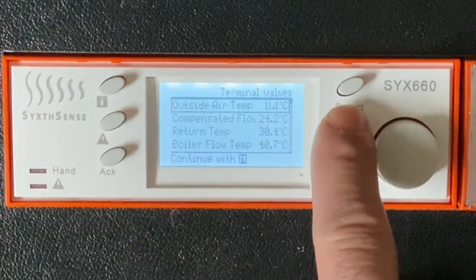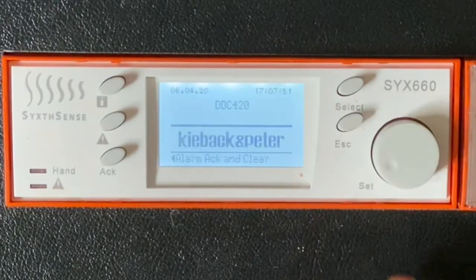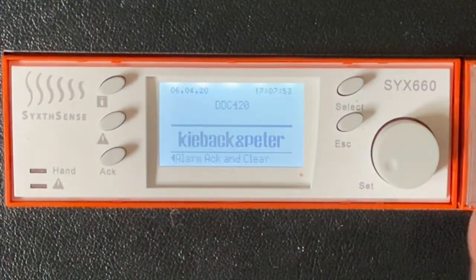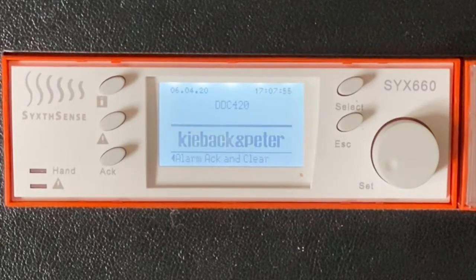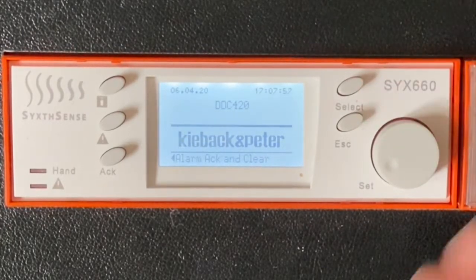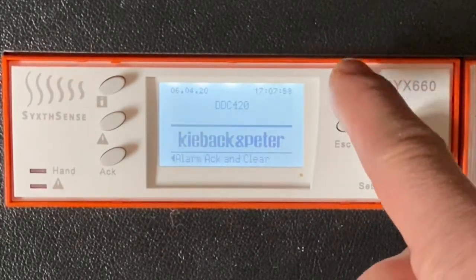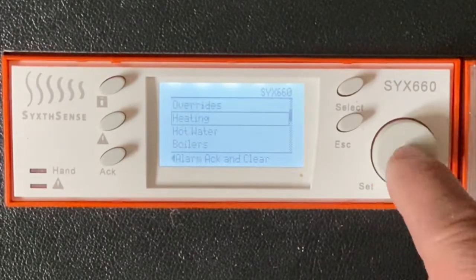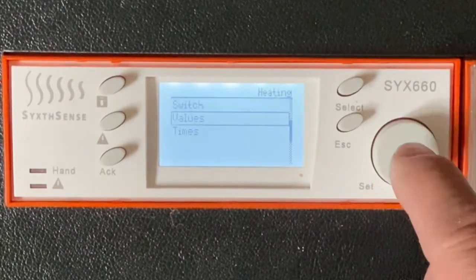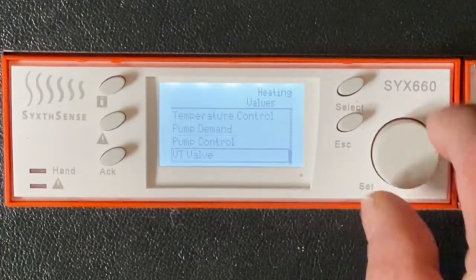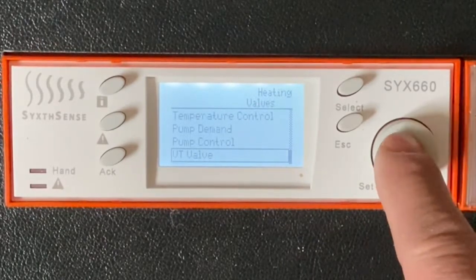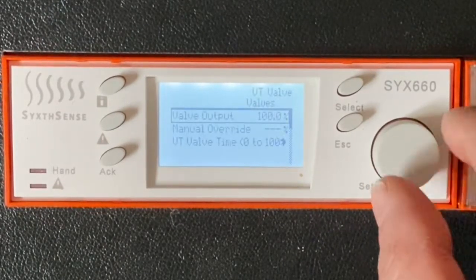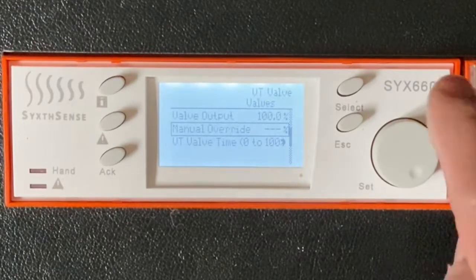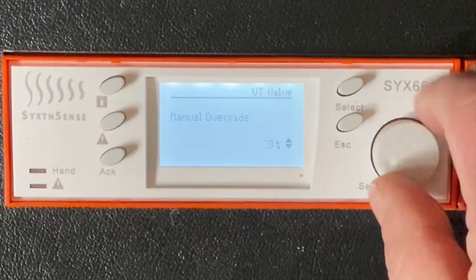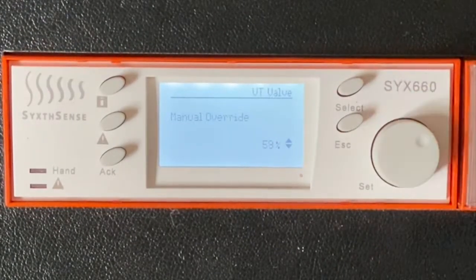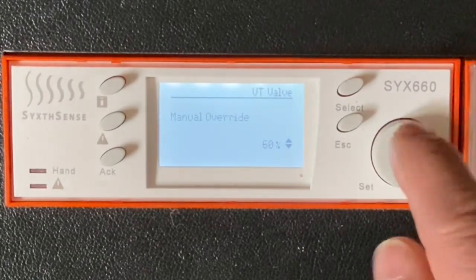Next thing I'd like to show you is how to test the variable temperature valve. Again, we're still logged in at user level 2, and for that we can make a manual override adjustment. So we press the select button, we choose heating, we choose values, and we drop down onto the VT valve, and we press on the wheel on the VT valve and we choose manual override. Press the wheel on manual override and it gives us the option to put a value in there. So I don't know, just arbitrarily put 60%.